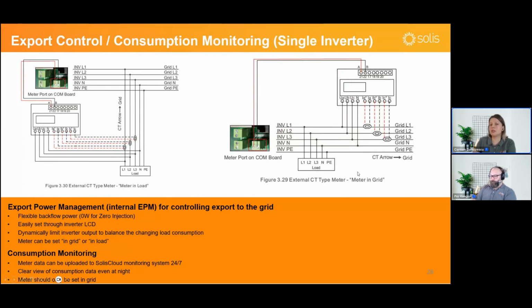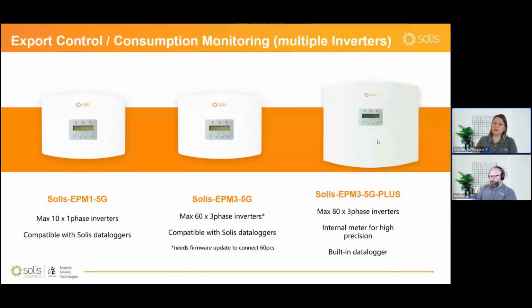When you have the meter set in grid, the logic changes a bit, and the generation of the inverter will match. The backflow power set for the inverter will have to match the output power measured here at the grid connection point. So this is the solution for installations with just one inverter.